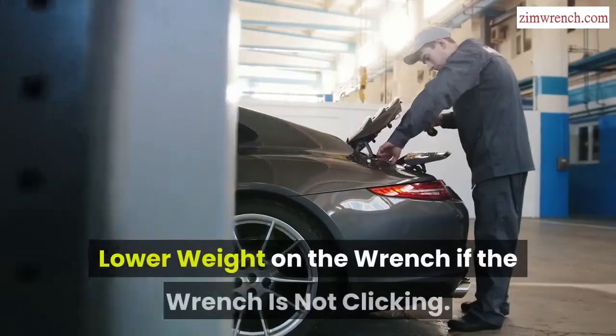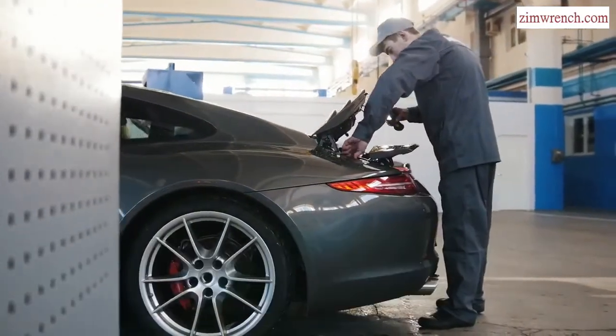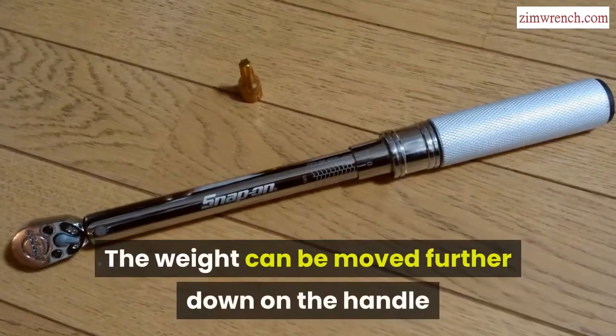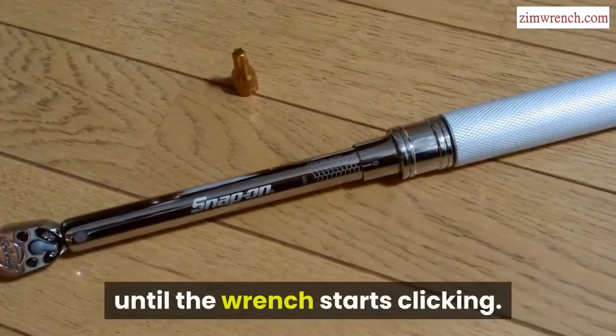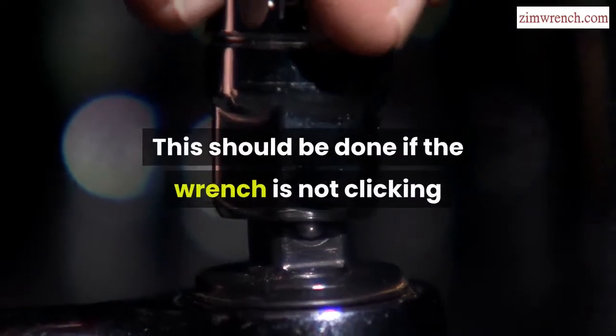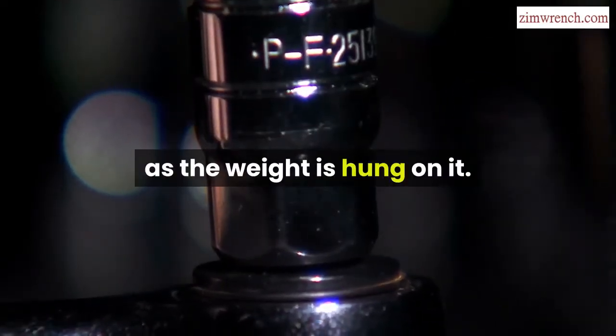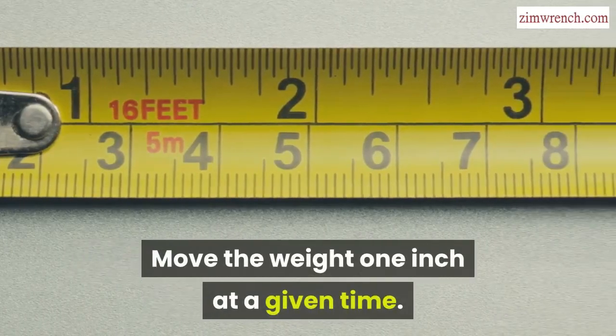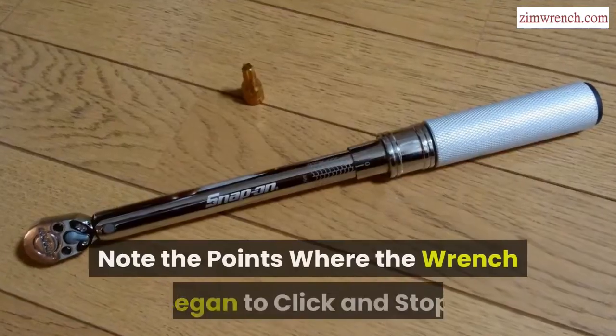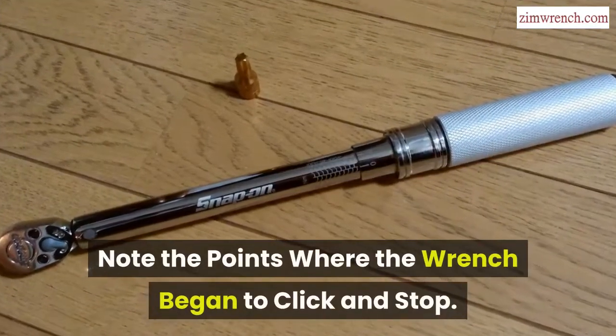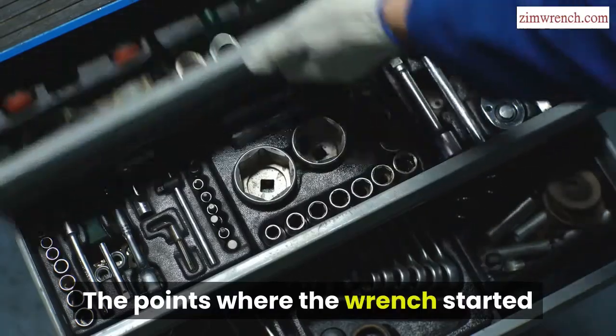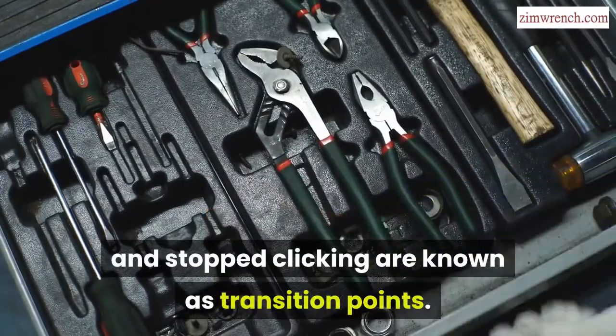Lower the weight on the wrench if the wrench is not clicking. The weight can be moved further down on the handle until the wrench starts clicking. This should be done if the wrench is not clicking as the weight is hung on it. Move the weight 1 inch at a time. Note the points where the wrench began to click and stop. The points where the wrench started and stopped clicking are known as transition points.